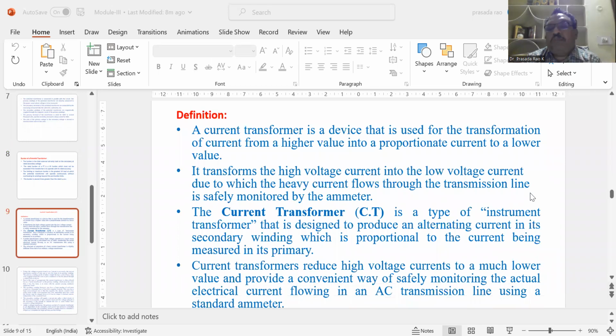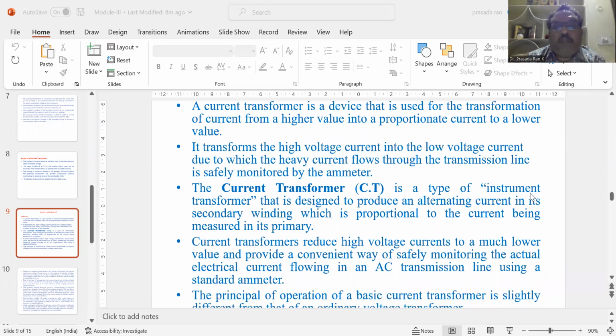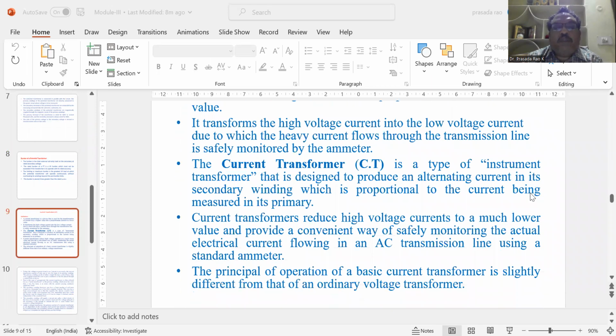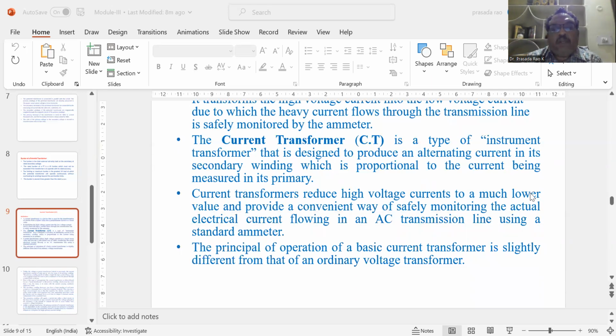The current transformer is a type of instrument transformer that is designed to produce an alternating current in its secondary winding, which is proportional to the current being measured in its primary winding. Current transformers reduce high currents to a much lower value and provide a convenient way of safely monitoring the actual electrical current flowing in an AC transmission line using a standard ammeter.